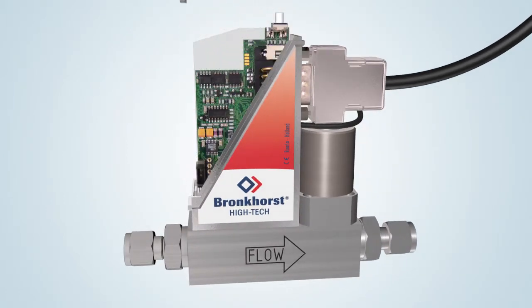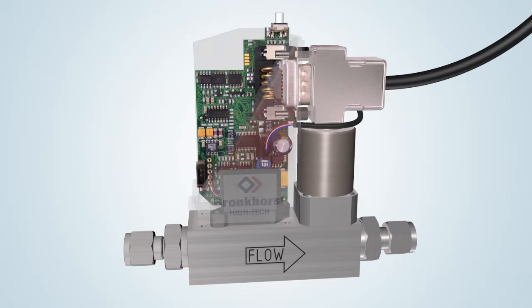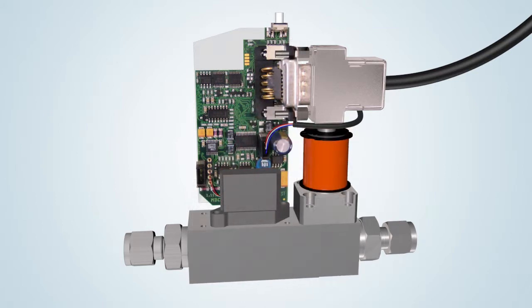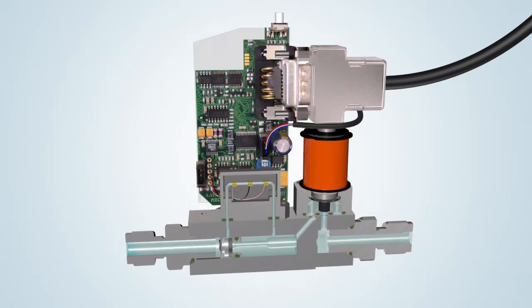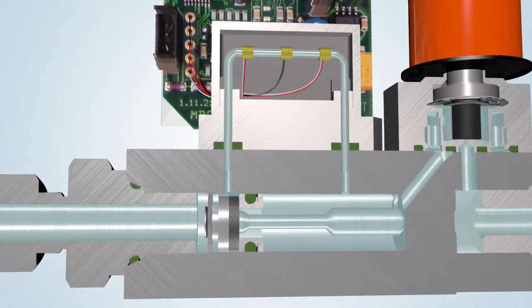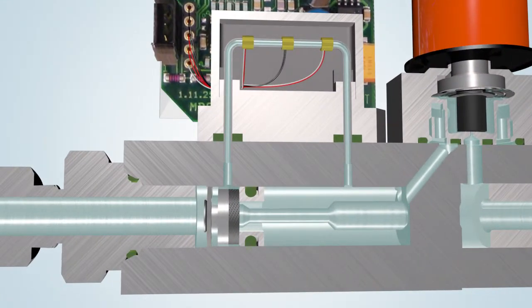Under the cover of the L-Flow MFC are the electronics made using SMD technology. The measuring part of the instrument consists of a patented laminar flow element combined with a thermal mass flow sensor.